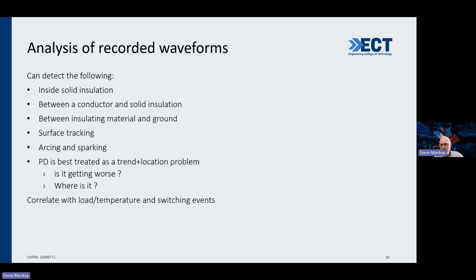Yes, a graphical view of what's happening is far better than text and numbers. People love graphics. Engineers love graphics. So when I say the trend is your friend, you look at the situation today with partial discharge, and then you look at it again in a month's time. If it's getting worse, then you say, hey, there's a problem here. If it's staying about the same, then there's probably not a problem. So at the end of the day, the trends are probably the most critical thing.